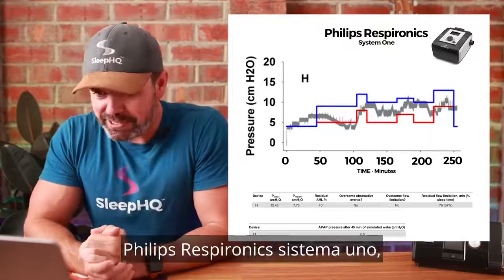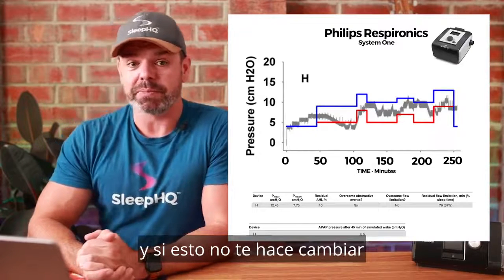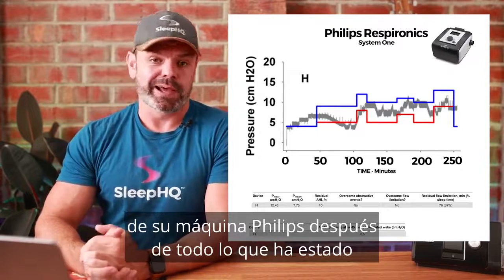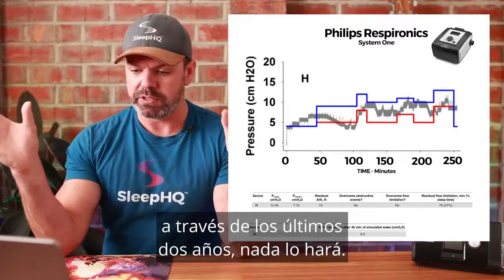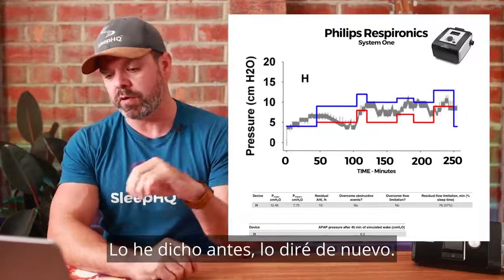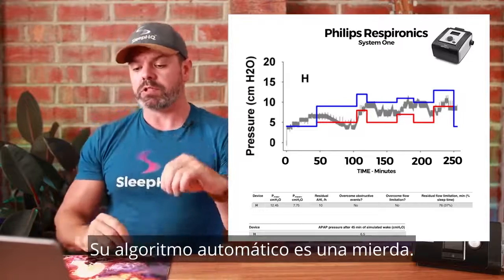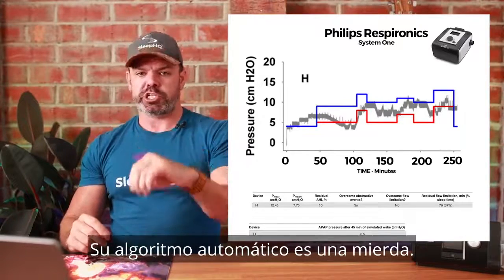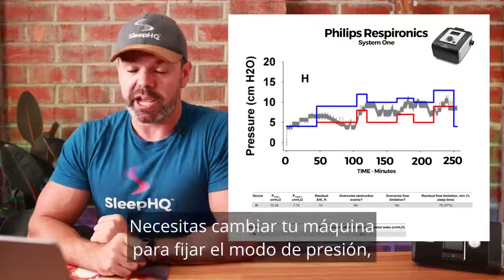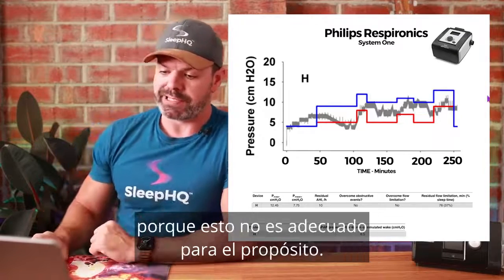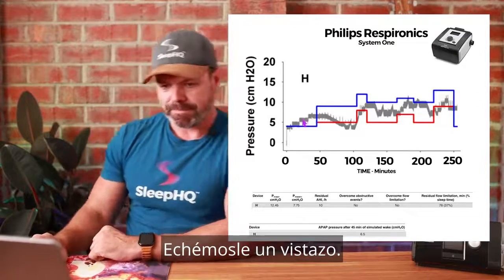Uh-oh. Here we go. Philips Respironics System One. And if this doesn't make you change from your Philips machine, after everything you've been through over the last 2 years, nothing will. I've said it before, I'll say it again. Their automatic algorithm is shit. You need to change your machine to fixed pressure mode because this is not fit for purpose. Let's have a look at it.